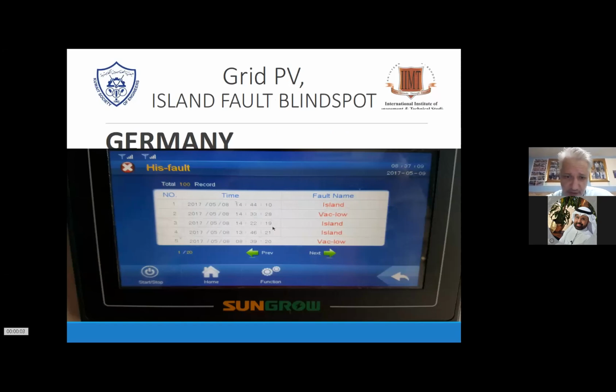What you do have in the old systems, I saw, this is an inspection, is the island phenomenon. So what happened is, during most of the underperformance issues I encounter, the system goes island, or shows it goes island, or for example, the AC has an undervoltage, a tripping point, low voltage, frequency hopping. This is sometimes actually caused by an ISO failure. So you have these phantom ISO faults, I call them. So if the system is not perfectly aligned, which we will see later on, into the earthing structure of specific transformer and inverter settings, then you will also have problematic issues which show up at the inverter, but in actual fact are a completely different problem.